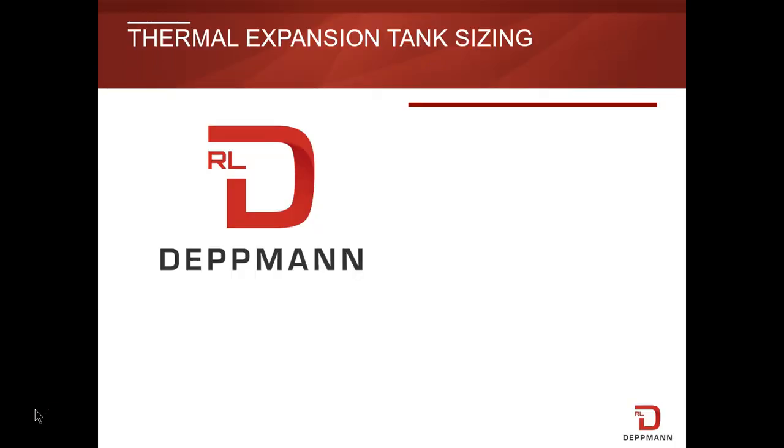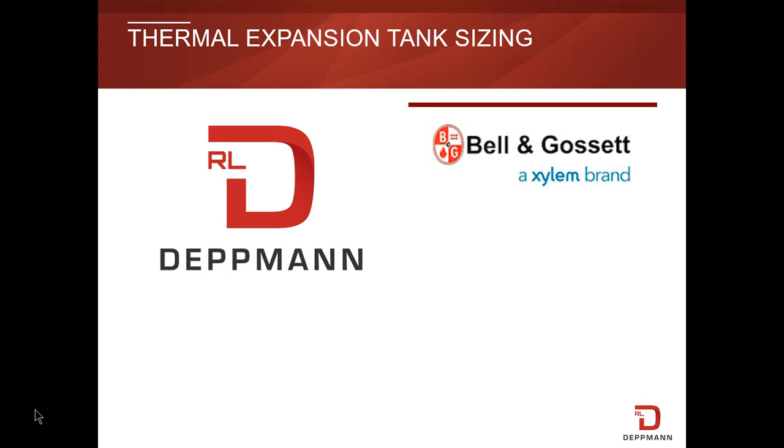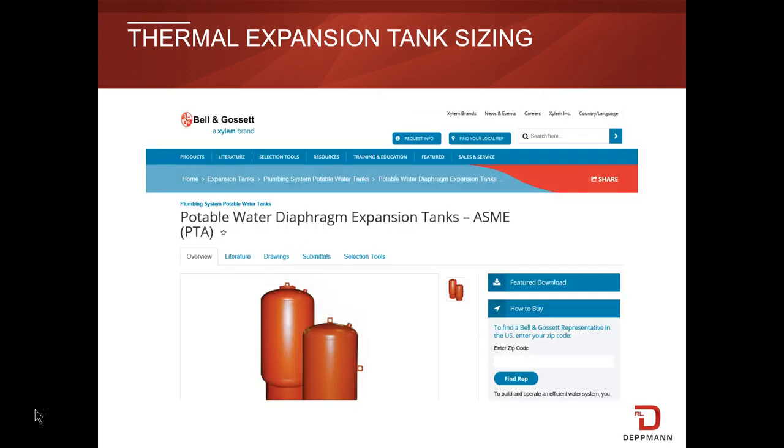Deppmann is the manufacturer's representative in northern Ohio and Michigan for Bell & Gossett, a Xylem brand. B&G provides both ASME and non-code thermal expansion tanks. The purpose of a thermal expansion tank is to manage the system pressure when heating water during periods of no use on systems where there's a check valve or backflow preventer in the cold water main.